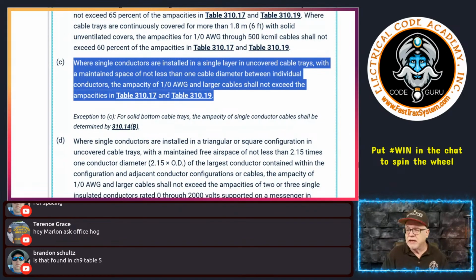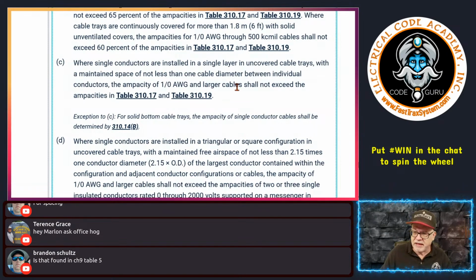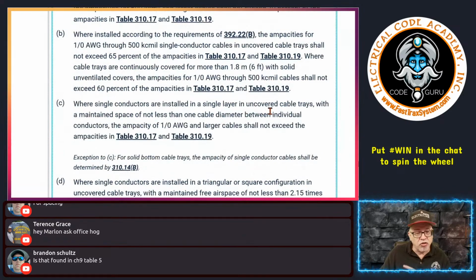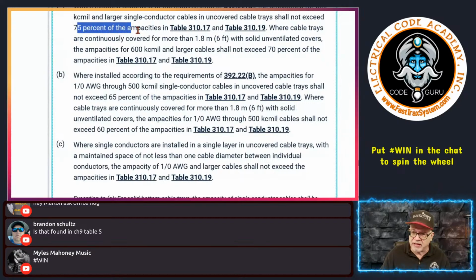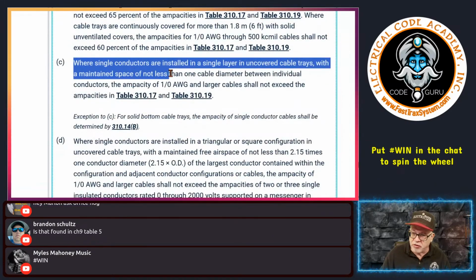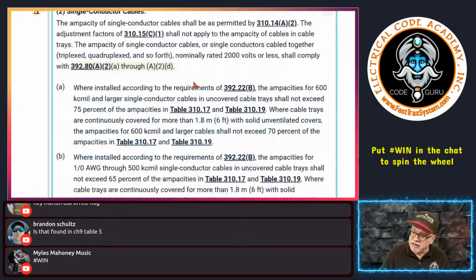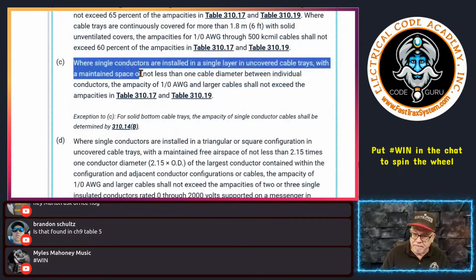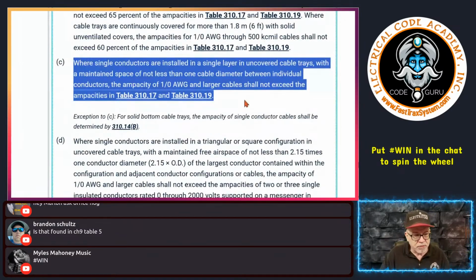By doing this, let's assume I do that, then it says, you know what? Then I can use the ampacity values in 310.17, okay? I can use those values. And because of these spacings, you'll notice something. I don't have a percentage. I don't have anything that affects the ampacity of the conductor, folks. It's not reducing it. I can use the ampacities from this table. And guess what? I also get to ignore 310.15(C)(1). That's a beautiful thing for right here if I design it that way, right?